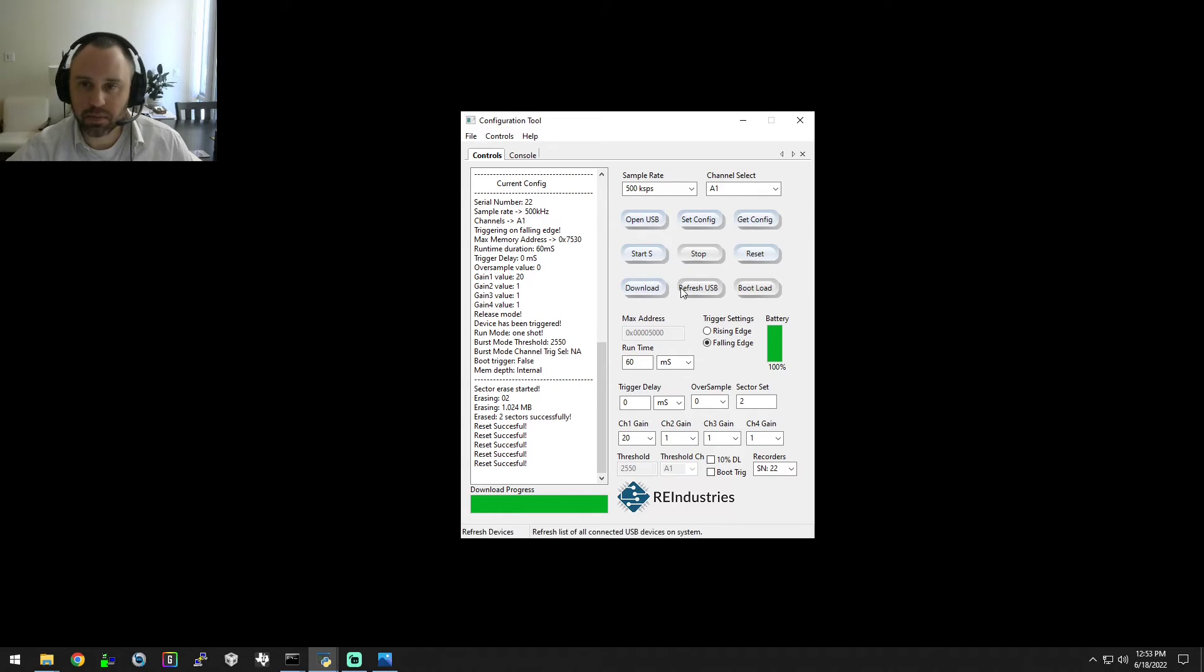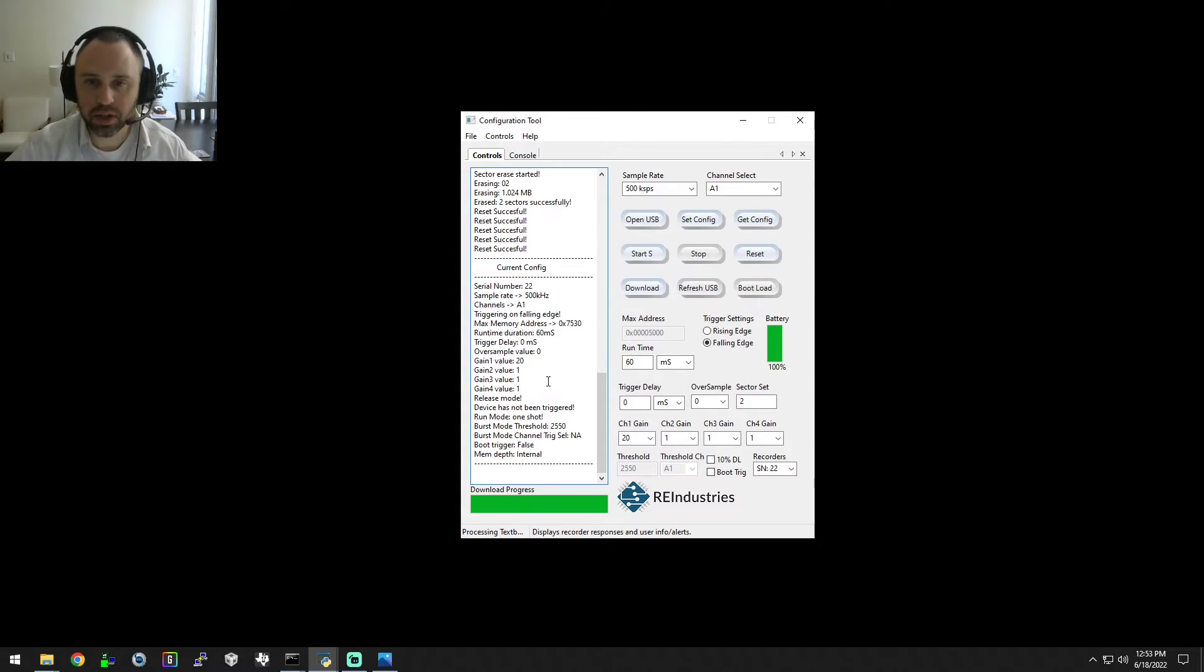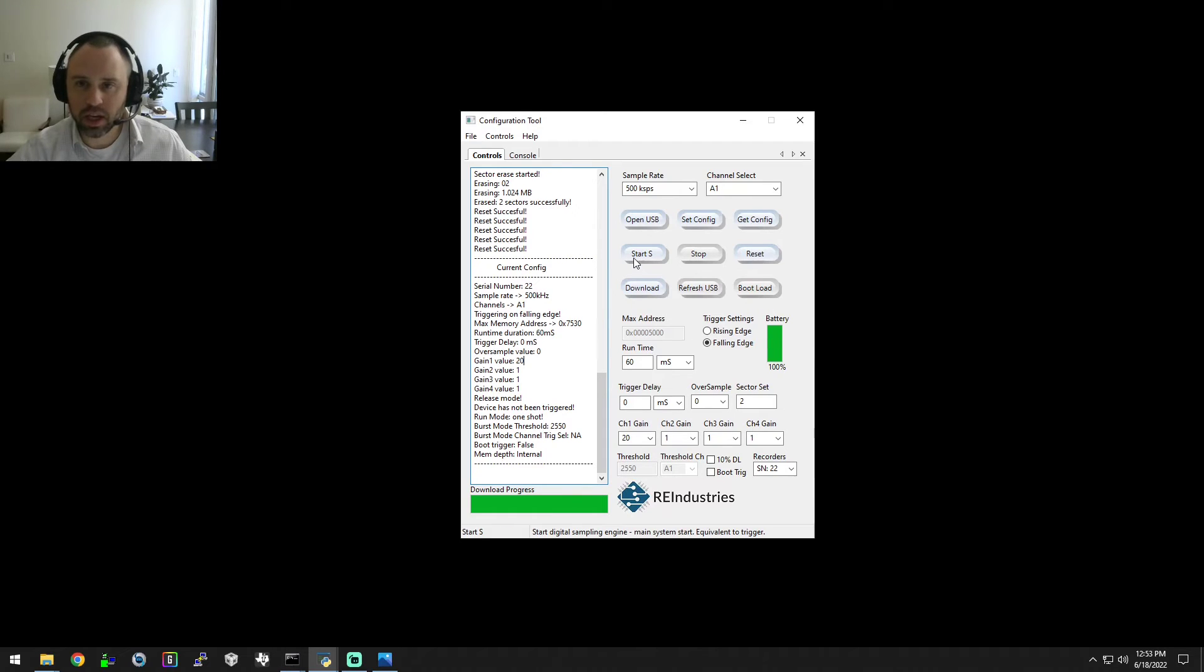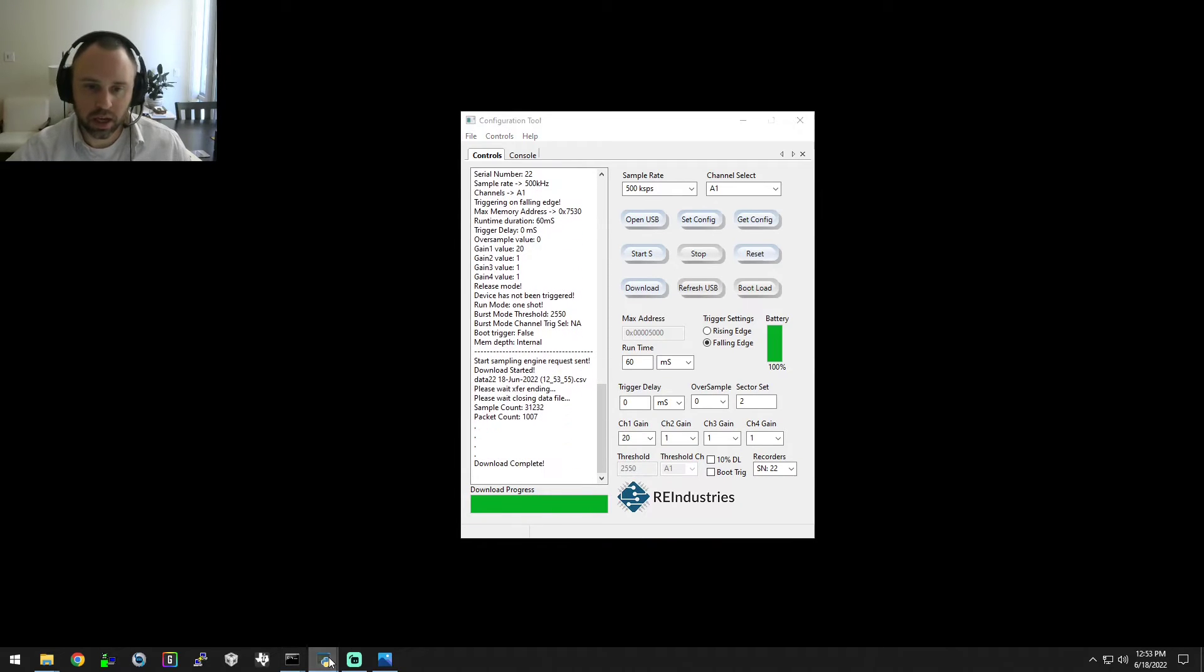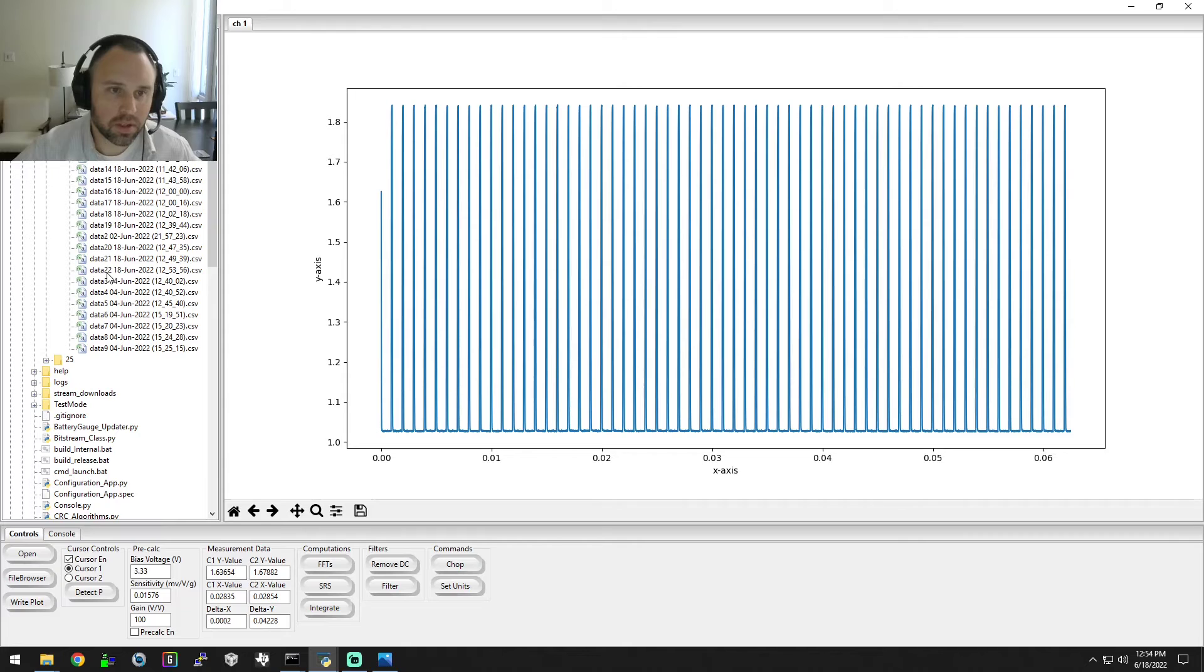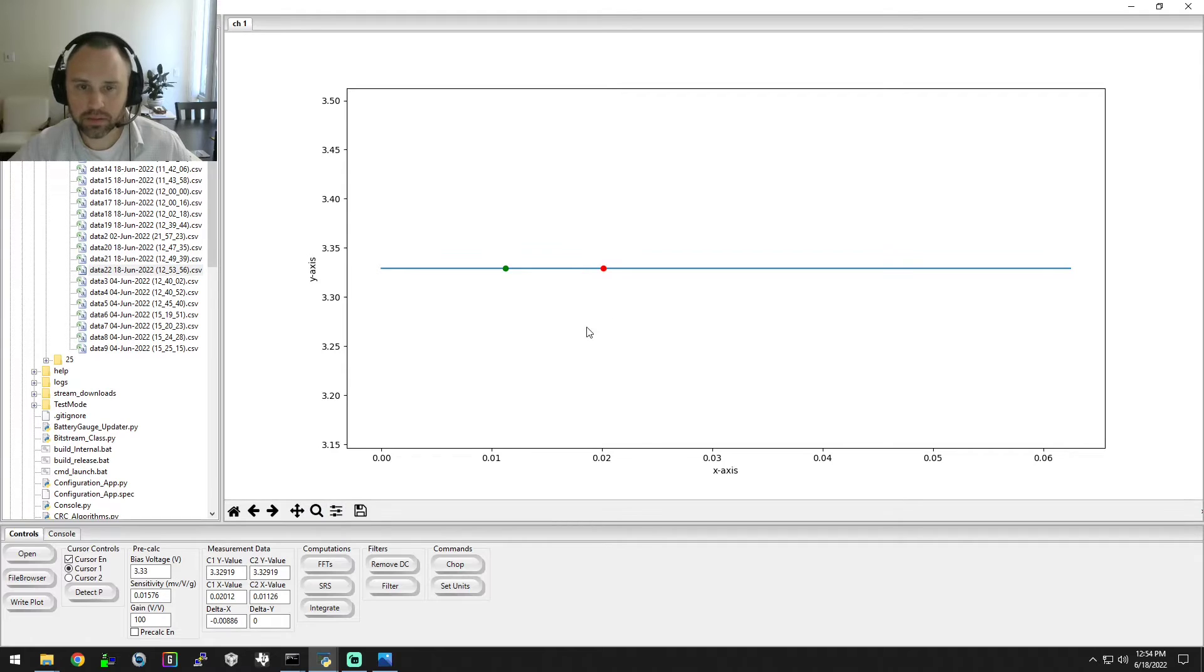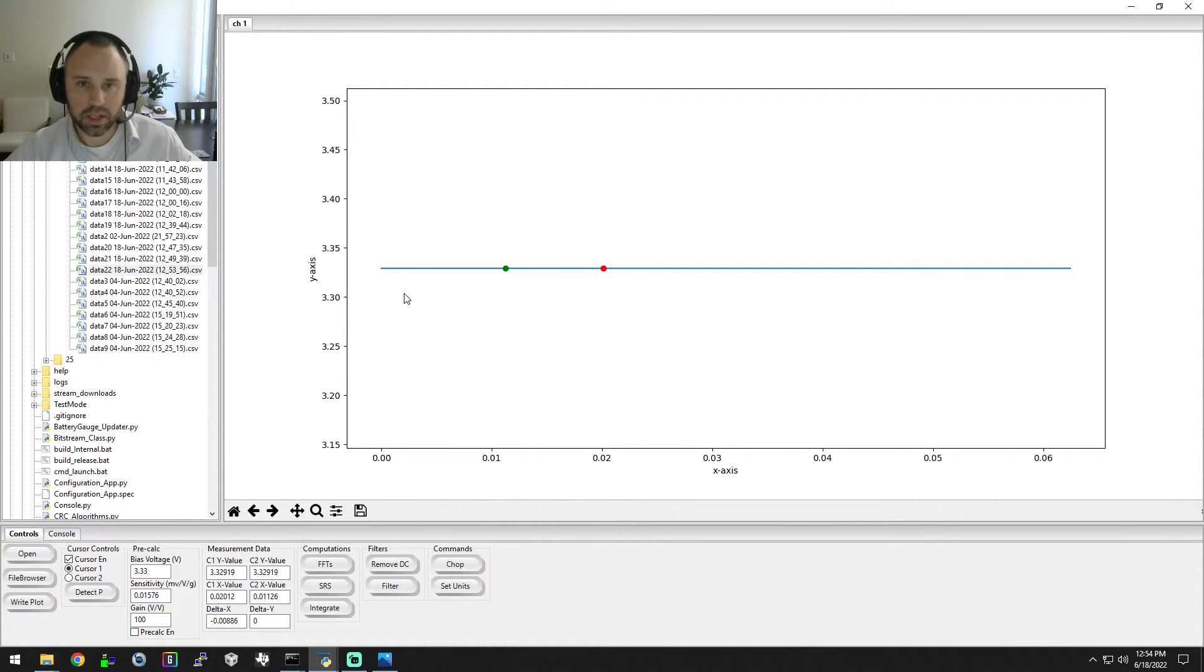For both operating modes it's the same. So post trigger memory does have to be managed a little bit by the user, but now we've got our recorder configured, our gain set. This is applied through the analog front end, so gain and DC offset are controlled digitally but they are implemented in the analog signal chain in the analog front end hardware. Now we'll do a start USB trigger command, download the data file and we will check our data file and plot which is 22. So you can see here we've got full channel saturation. We applied a gain of 20, the channel is offset already pretty high and this gain of 20 saturated the channel so we can't get any information.